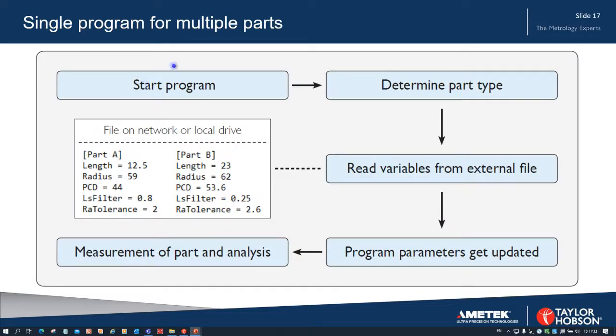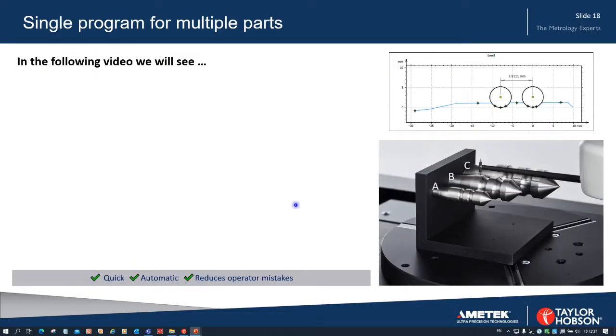The way it works then, the whole process that we've just been talking about: we start the program and we determine the part type either by barcode or by sampling the surface or by telling the system which part we're measuring. In each case it will read the variables about that part from a database or from a file held locally on the network. Note that the information about the part doesn't just include the length or dimensions of the part, but it also includes other things to do with the analysis. So we could choose how we want to analyze that part. In this case we're using a short LS filter, short wavelength filter of 0.8 millimeters, but for Part B here we're using a filter of 0.25 millimeters. So all of that can be kept in the company database and called up just by the barcode or the other methods before we start the measurement. So let's have a look at the way we can automatically detect which parts are there.